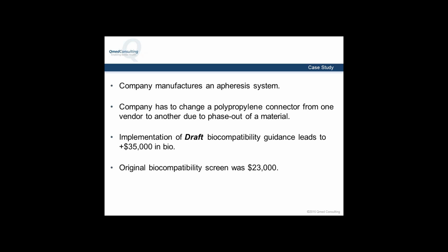So it went from one resin to another. No colorants, no additives, just straight polypropylene. You look at an FTIR, they were indistinguishable from one another. The company had a master file on site with FDA, although it was in compliance with USP requirements for Class 6, not necessarily 10993 requirements. We went to FDA, said, hey, the company's changing this out, and we want to reference their material, and we ran a cytotoxicity screen. Everything was fine. FDA came back and said, hold up there. We need you to do a full screen on this.